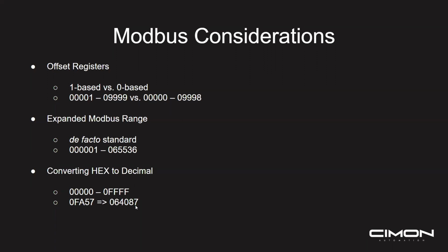And then I guarantee you that will communicate with the hexadecimal address. The packet will take care of the translation for you. I don't want to say it's magic, but that's just how the protocol was developed, of course. I've had my fair share of hardships dealing with ModBus, and I noticed that you can just take care of the hexadecimal address by transferring it to a decimal form. Our XPanel Designer doesn't support hexadecimal ModBus, so you can do something of this nature to overcome that obstacle.